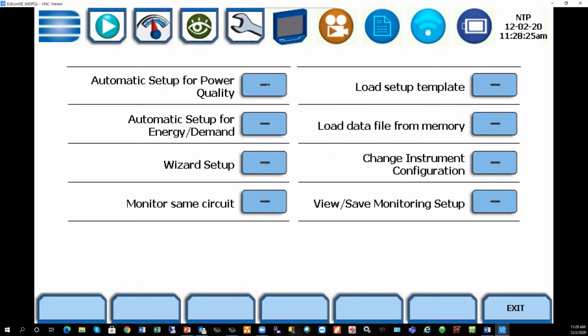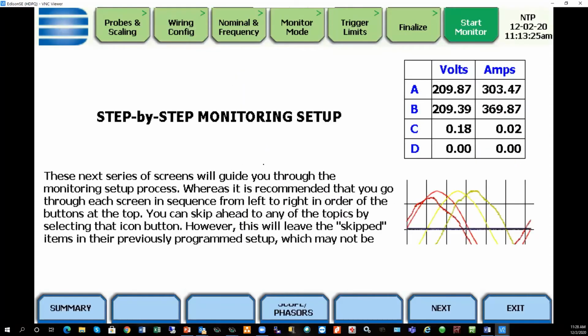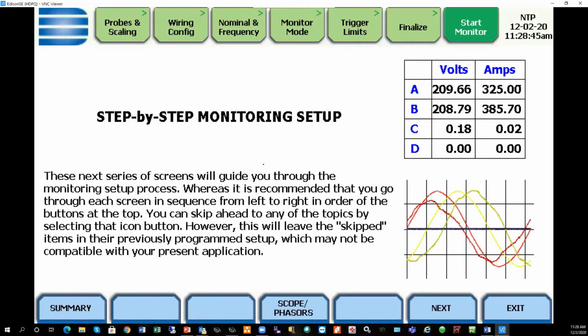You can use the automatic, but what I would suggest, and Ken, my colleague, can chime in as well, is what we call the Wizard Setup. The Wizard Setup gives you more flexibility as far as setting up the instrument. And there are a couple of things you want to be aware of, especially if you're going to be fully compliant with IEEE 519-2014. As Ross mentioned earlier, there's VTHD, and then there's TDD, which is total demand distortion. Voltage harmonic distortion is pretty straightforward. It's usually referenced to the fundamental, or might be referenced to RMS, depending on what the application is.